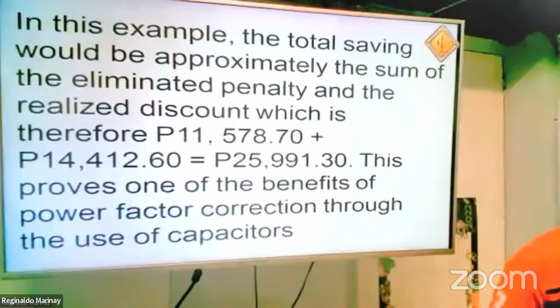Okay, this proves one of the benefits of power factor correction through the use of capacitors. You have to add these two, so that is around 25,991.3 pesos. That's how big your saving is - that is your total saving. You eliminate the 85% penalty, and you increase the power factor, so you have a discount instead. Therefore, your total saving is the sum of these two. You lost the penalty, and you even gained a discount, because you increased the power factor.